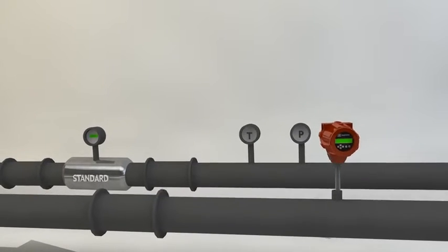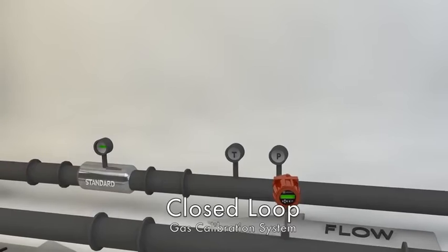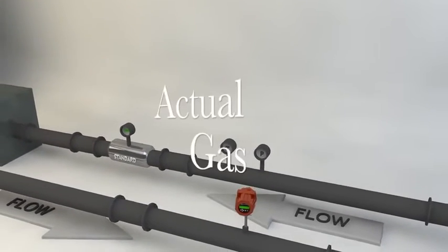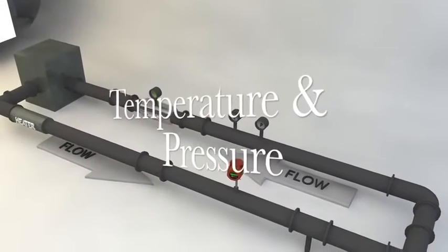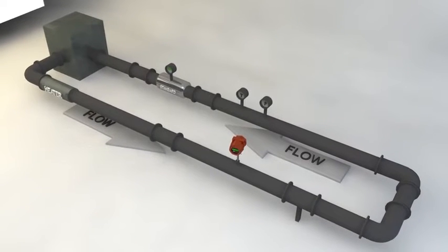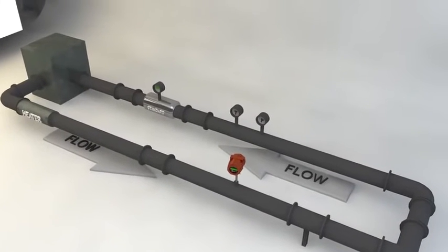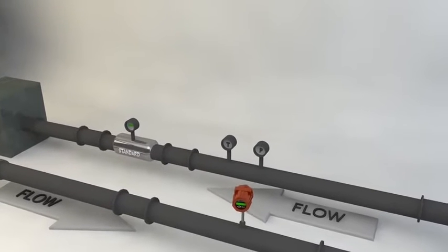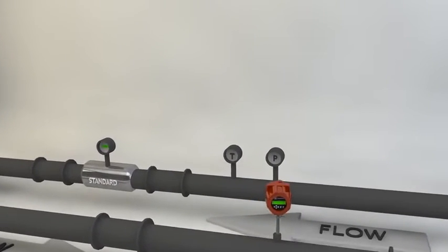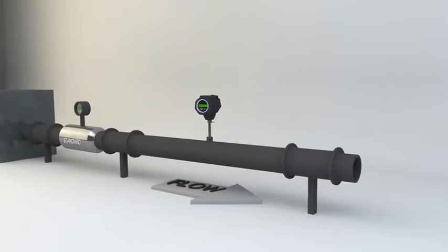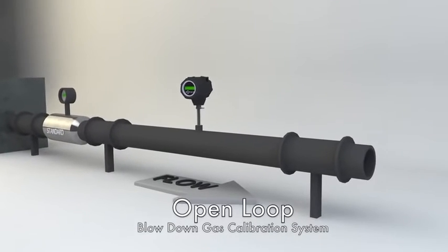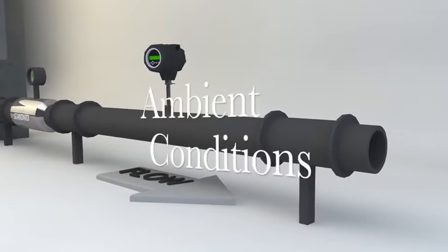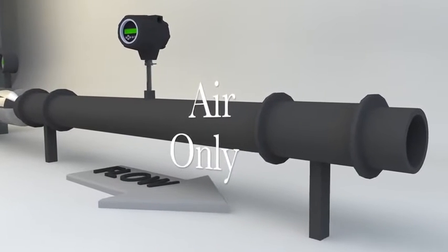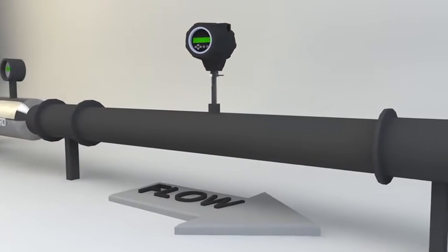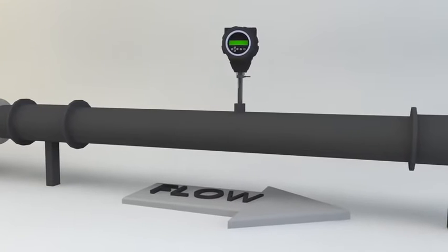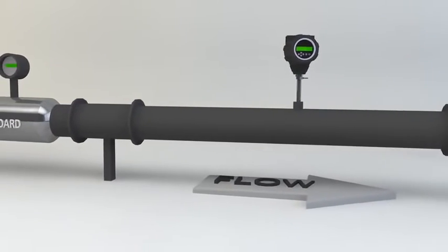Sierra Instruments uses a state-of-the-art NIST traceable closed-loop gas calibration system that is charged with the actual gas to be measured and set to the actual temperature and pressure of the end-user application. This perfectly simulates the customer application environment for a quality calibration, assuring the highest possible performance in the field. Be careful of blow-down or open-loop calibrations, as they operate at ambient conditions and are only done on air. As a result, any other application environment will be inferred indirectly, introducing uncertainty, and thus produce a less accurate meter.